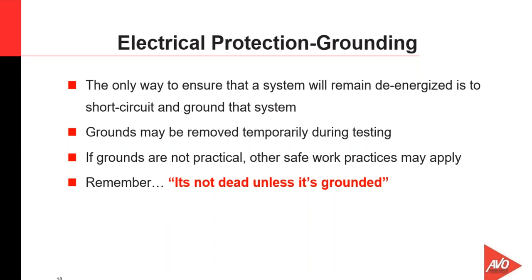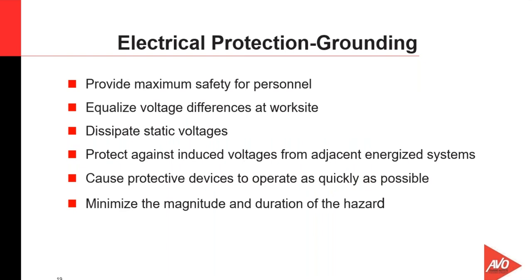Grounds can be removed during testing. It would have to be. If we're testing that cable, we would have to take the grounds off of it, but they need to be put back on once the test on that cable is completed. If grounds are not practical, then we work in an exception where other safe work practices may apply in the use of barriers and other methods of protection. Remember one thing, and this has been around a long time, it's not dead unless it's been grounded properly. Grounds provide maximum safety for personnel because we equalize the voltage in the work site.